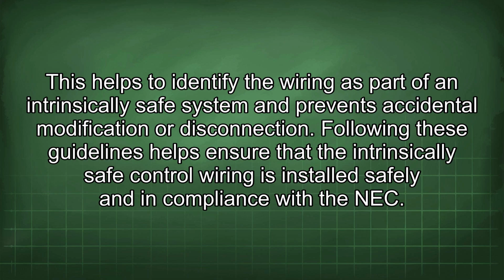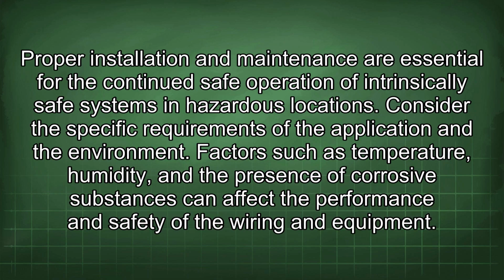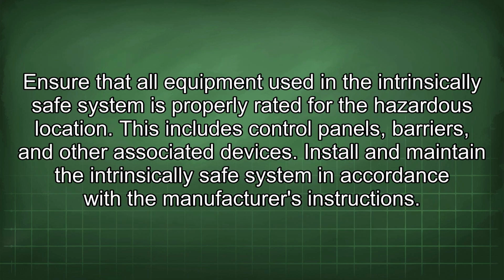Following these guidelines helps ensure that the intrinsically safe control wiring is installed safely and in compliance with the NEC. Proper installation and maintenance are essential for the continued safe operation of intrinsically safe systems in hazardous locations. Consider the specific requirements of the application and the environment. Factors such as temperature, humidity, and the presence of corrosive substances can affect the performance and safety of the wiring and equipment. Ensure that all equipment used in the intrinsically safe system is properly rated for the hazardous location.